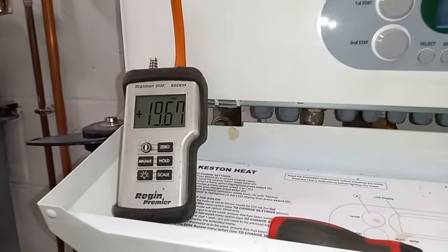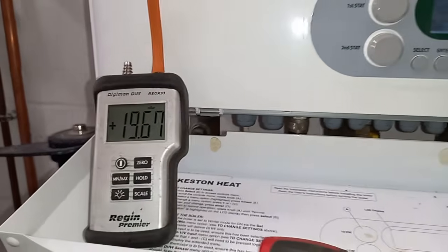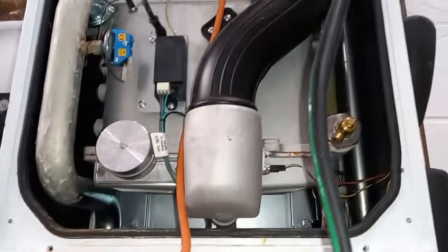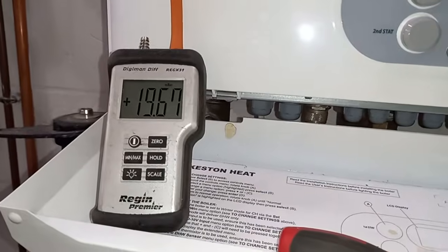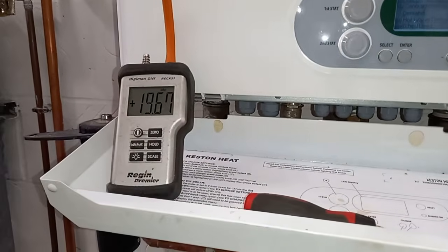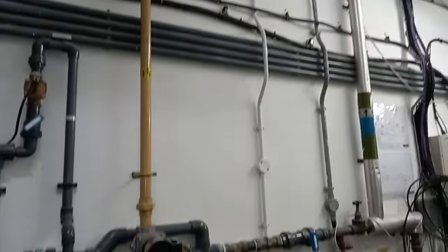There was enough gas in my system, so when I attached it, I didn't need to top it up much, but I can tweak it because I should be on 20 or 21 millibar for this. Even when you're doing local, you carry out your volume calculation and work out what you're allowed. So we're going to leave our gauge on, not take it off and put it back on. It's on, so that's why we're going to do our first tests.